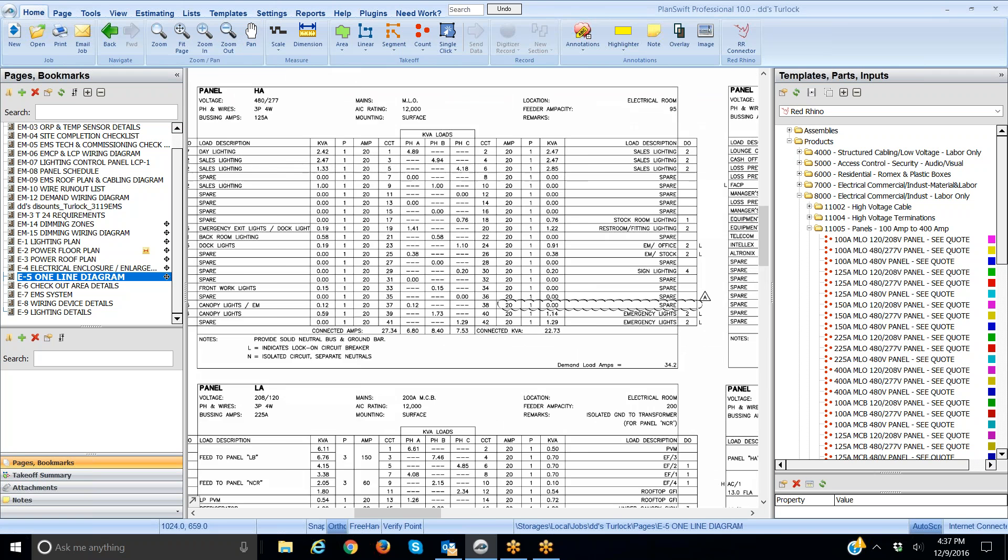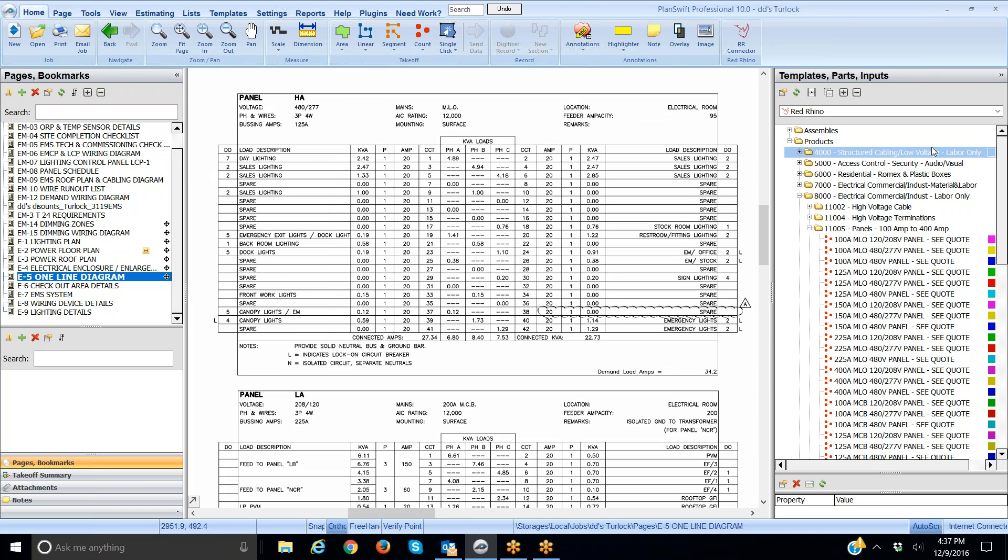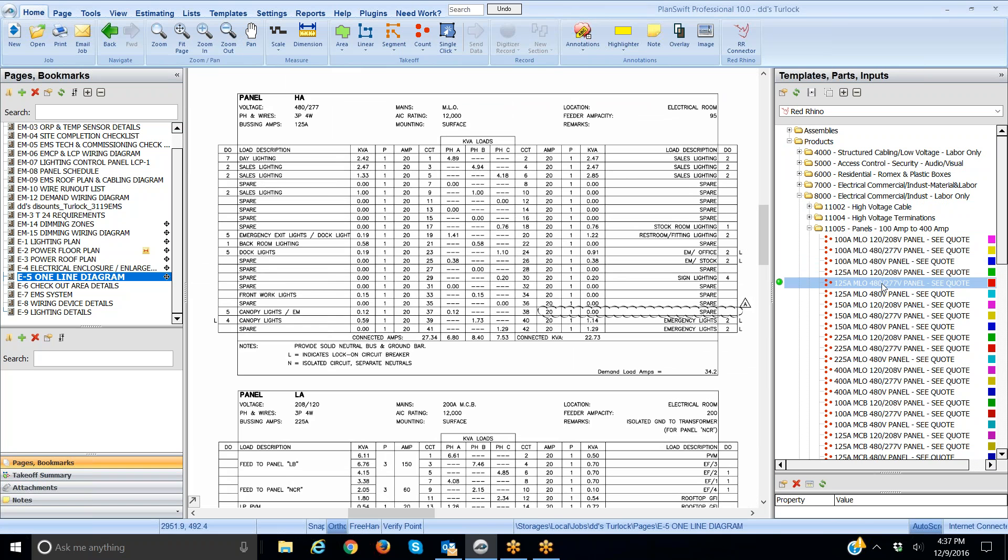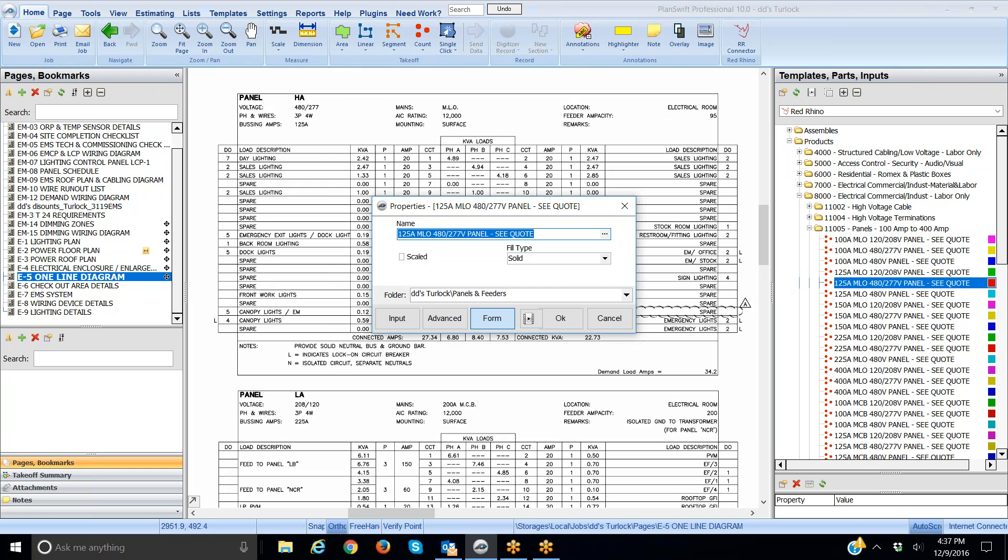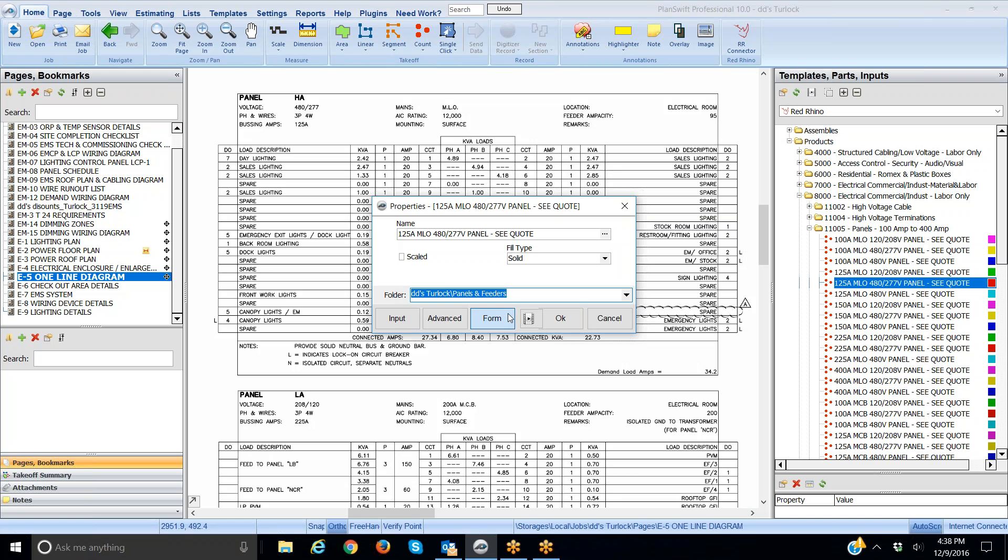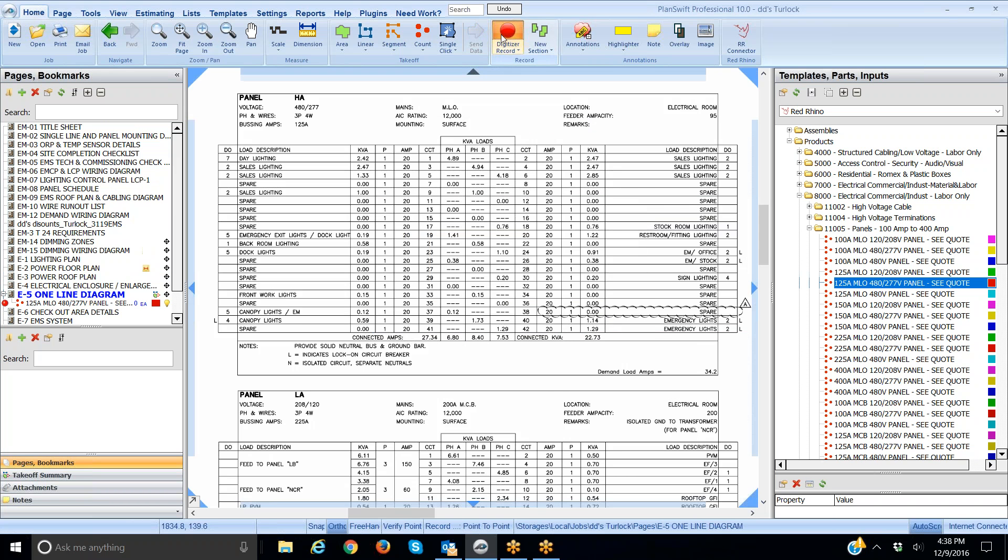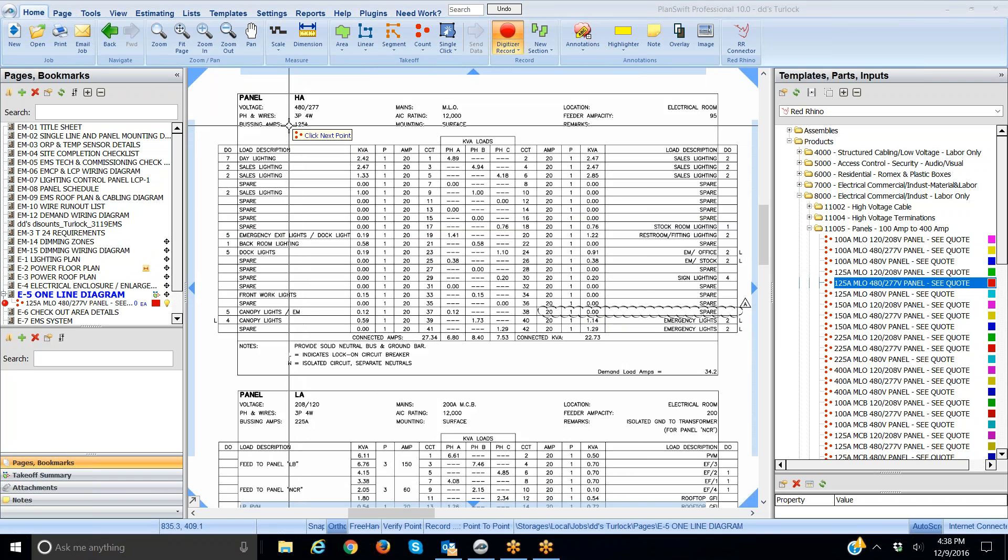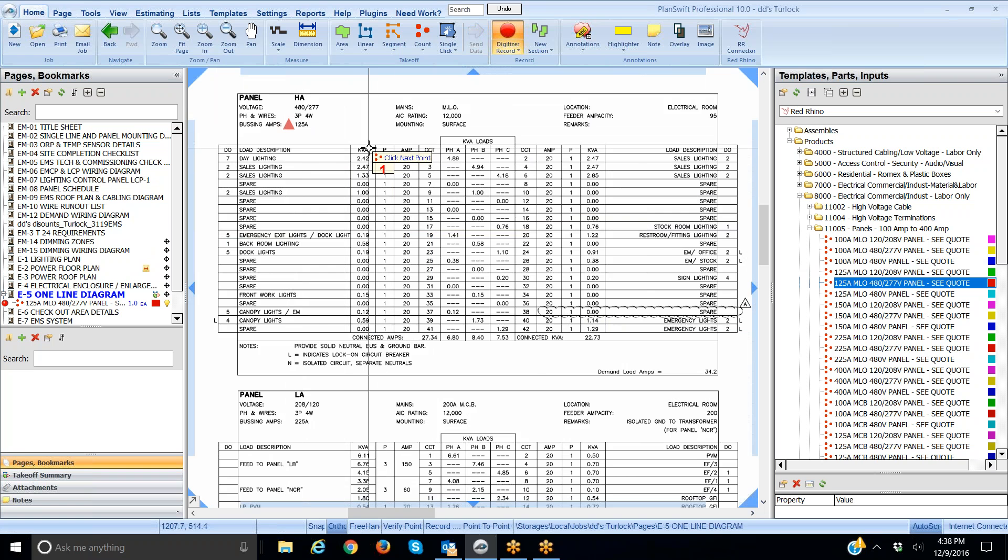I'm going to zoom in on these plans. This is a 125 amp panel. I'm going to click on the 125 amp panel. That one's 277, 480 volt. I'm going to click on the green dot to digitize. When I do it asks me what section I want this to go in. I set up this Red Rhino estimate already with sections which were imported into PlanSwift. Each time that you select something it asks what section you want it to go in. This was already preset for panels and feeders. I'll click OK and it starts digitizing. I'm just going to click right here next to the panel size and it digitizes with a little mark.